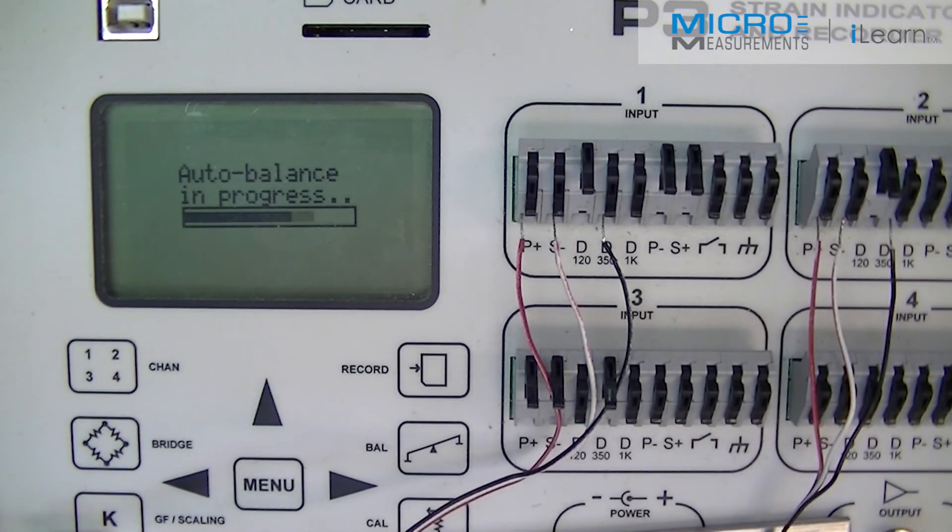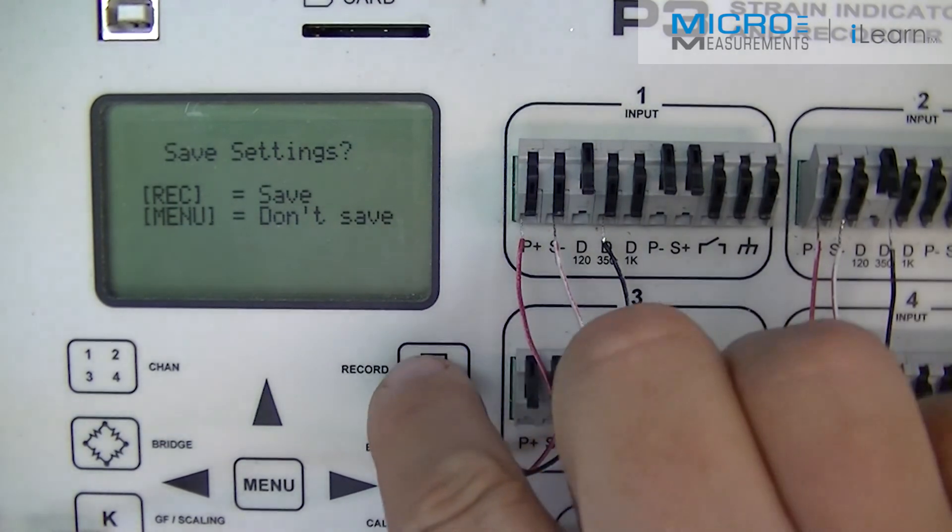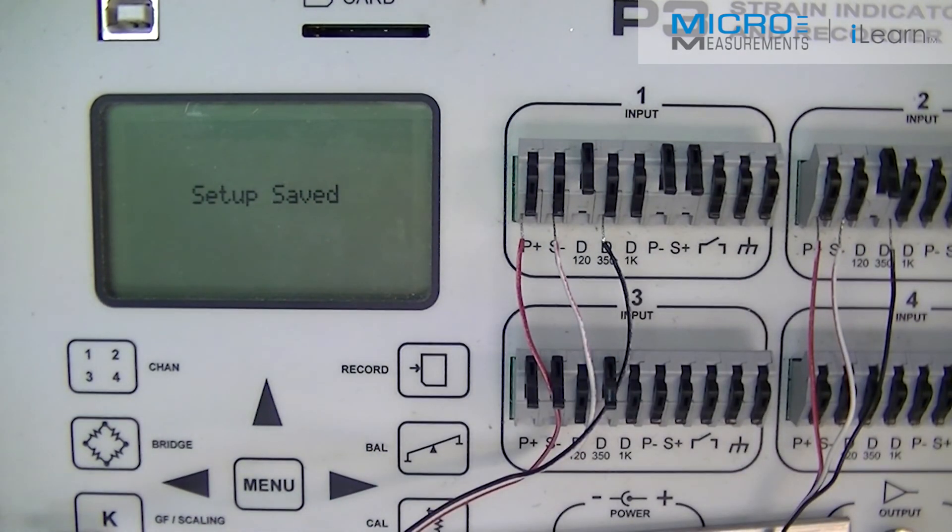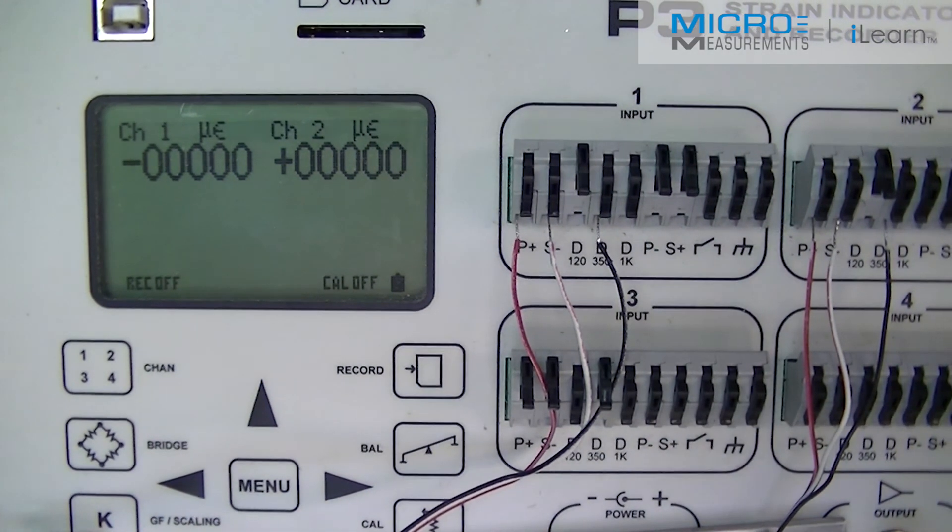We're going to balance both here under no load conditions. I can save the setup. And you'll notice that both channels are indicating zero strain.